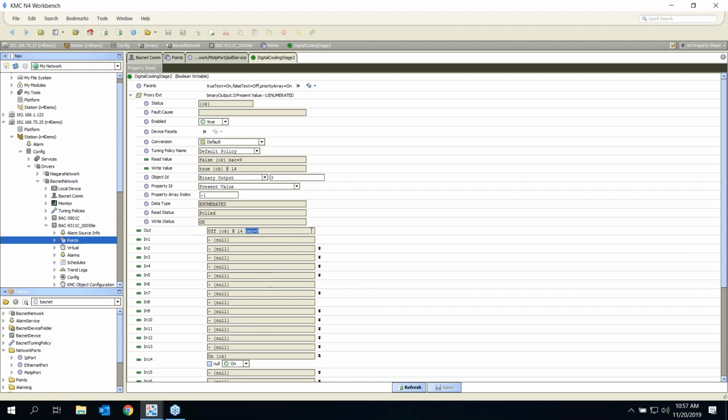If you have a thermostat that's writing to the same object or some other controller on the network, if you're going to implement policies where you do max write times and things like that, then you get the teeter-totter effect or the ping pong, where you tell it to do one thing and something else tells it to do the opposite. Then it can be helpful maybe to have that priority array on there as well.